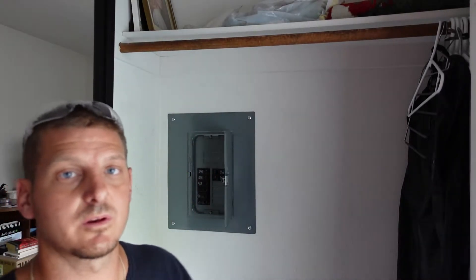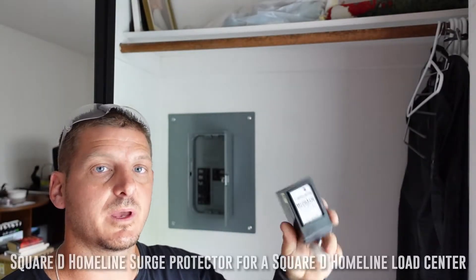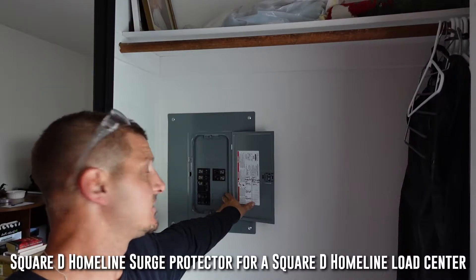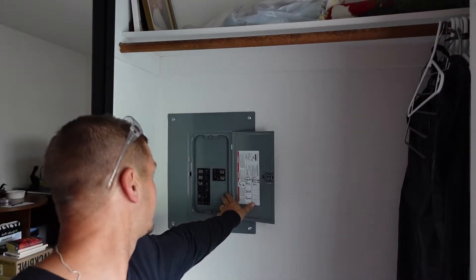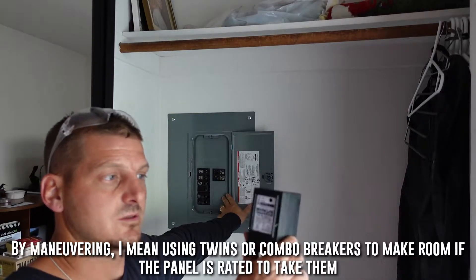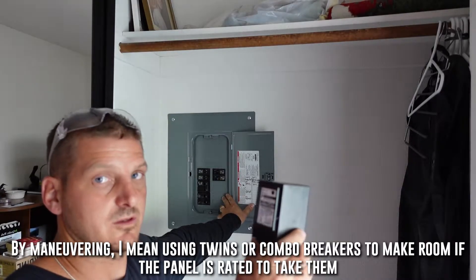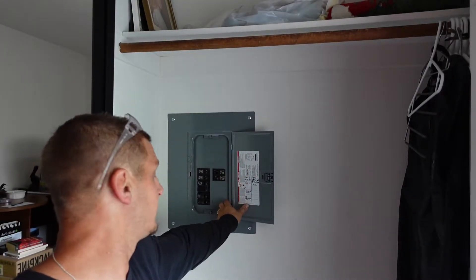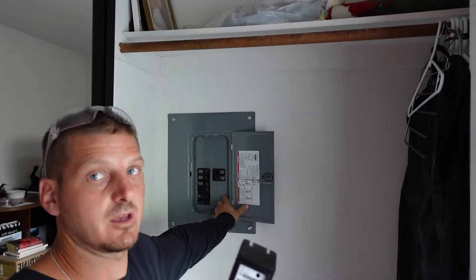Welcome to the Electrical Solutions YouTube channel. Today we're going to be adding a surge protector for a Homeline Square D panel into this panel. We do have open spaces in the panel so we can add it without doing any maneuvering. This specific surge protector is UL listed for the Homeline series panels — it's not UL listed for any other one.